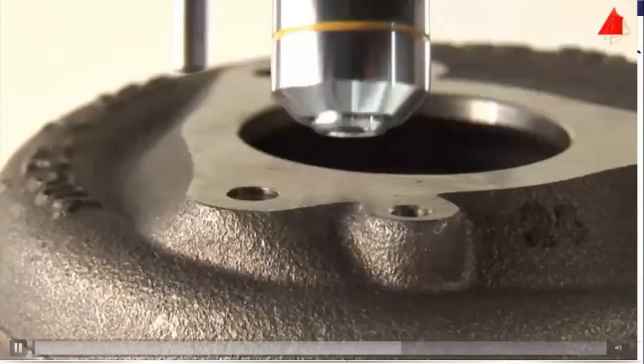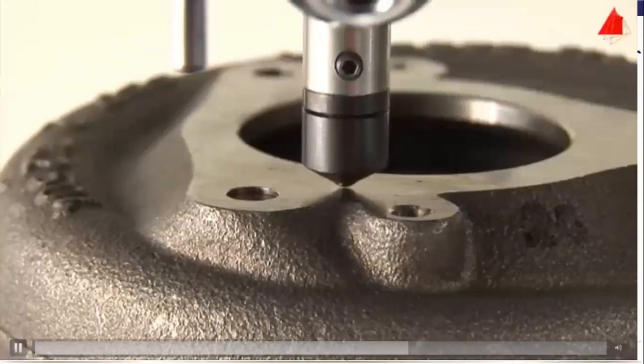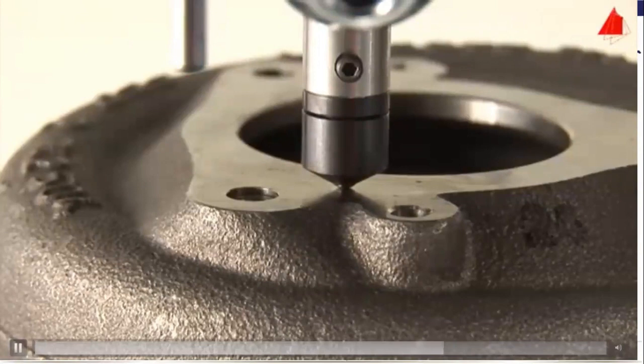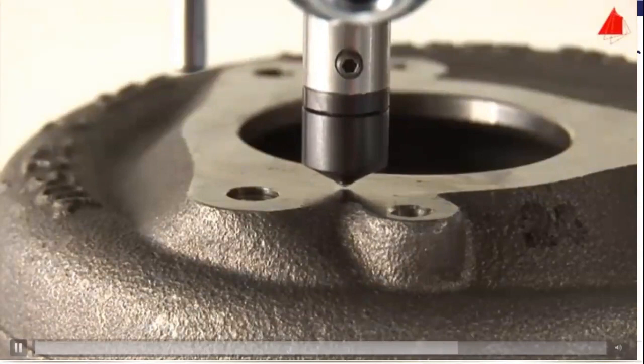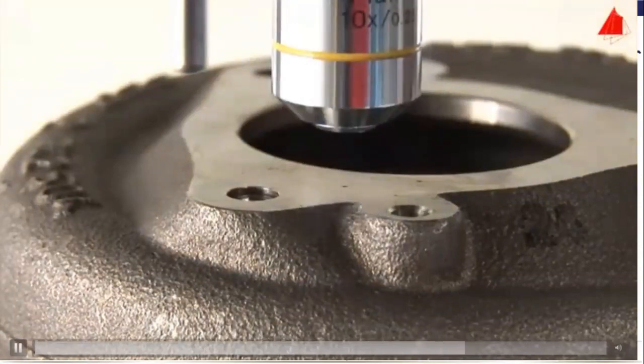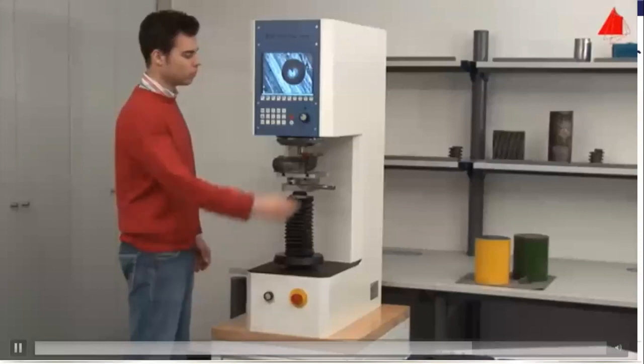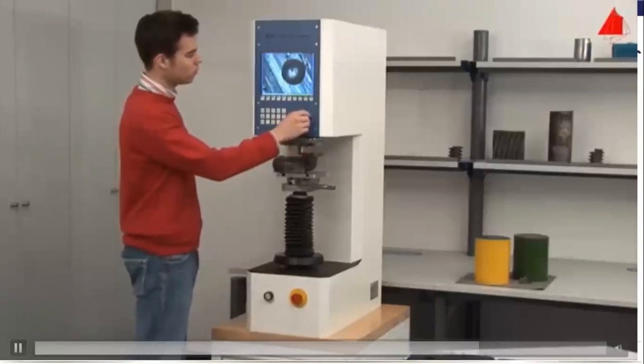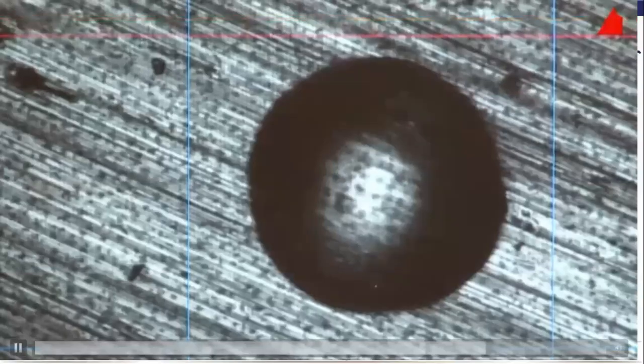The testing machine rotates the lens back to its resting position and places the spherical indenter carefully on the test piece surface. Gradually and shock-free, the test force rises to its specified value. After maintaining the test force for a certain time, the indenter automatically lifts off again and the microscope lens pans back to its former position. The indentation can now clearly be seen on the monitor. With the control knob, the tester places 4 measuring lines on the edges of the indentation to measure its diameter.